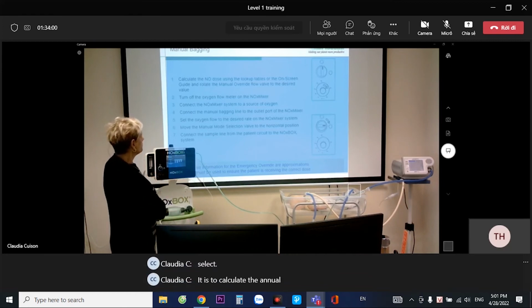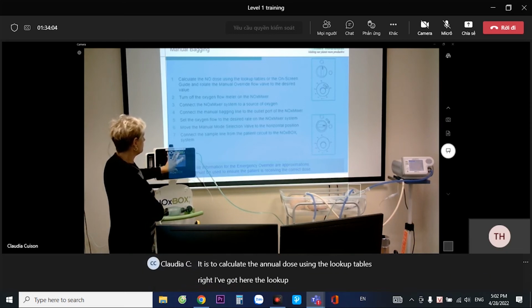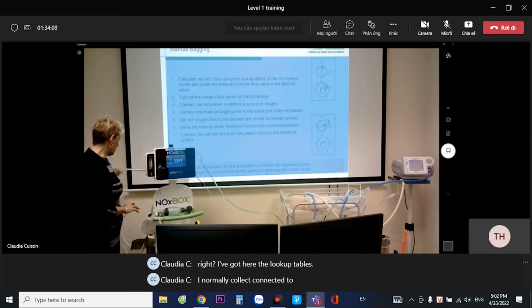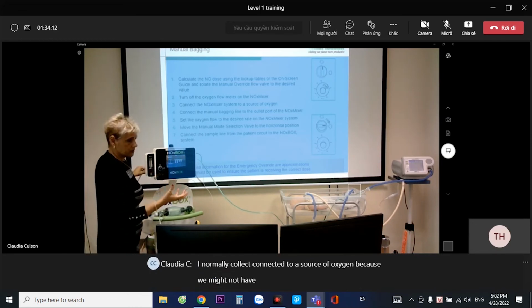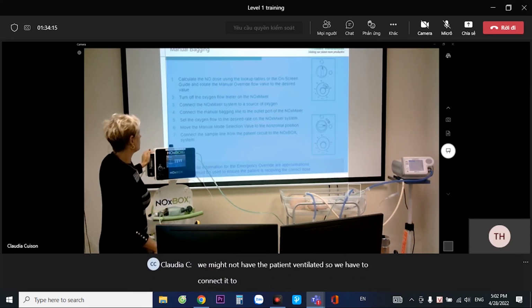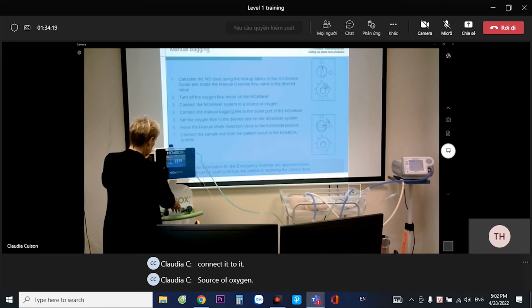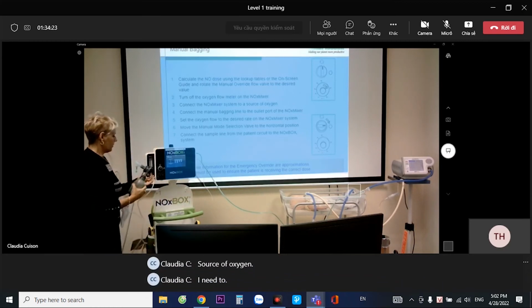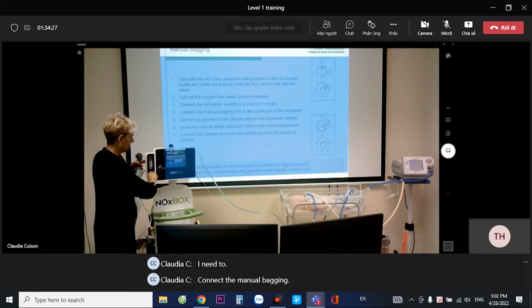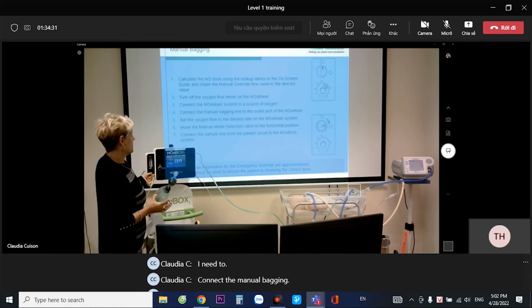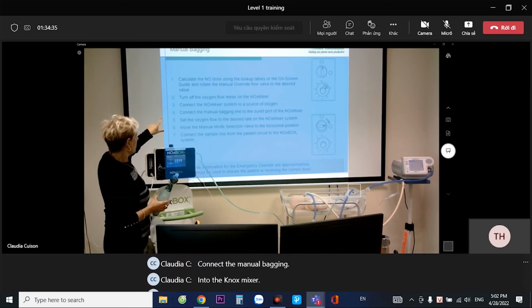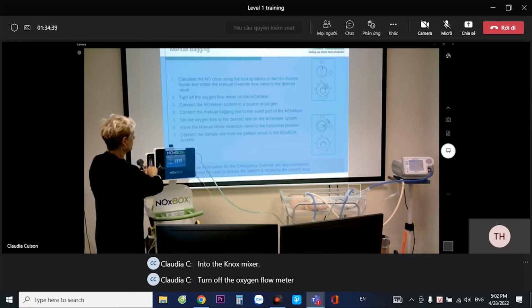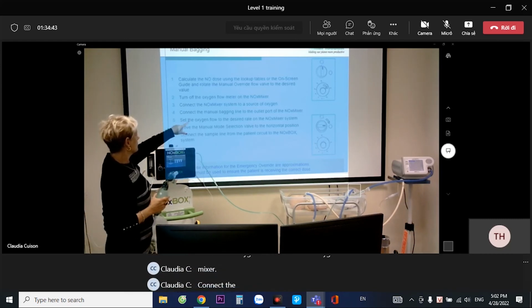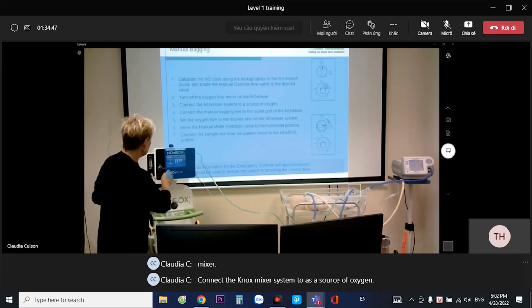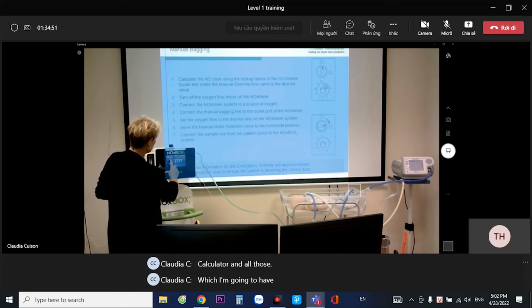to calculate the NO dose using the lookup tables, right? I've got the lookup tables here. I normally connect it to a source of oxygen because we might not have the patient ventilated, so we have to connect it to a source of oxygen. I need to connect the manual bagging into the NOxBOX. Turn off the oxygen flow meter of the NOxBOX. Connect the NOxBOX system to a source of oxygen. Calculate the NO dose, which is normally, people use 5 or 10 liters per minute.